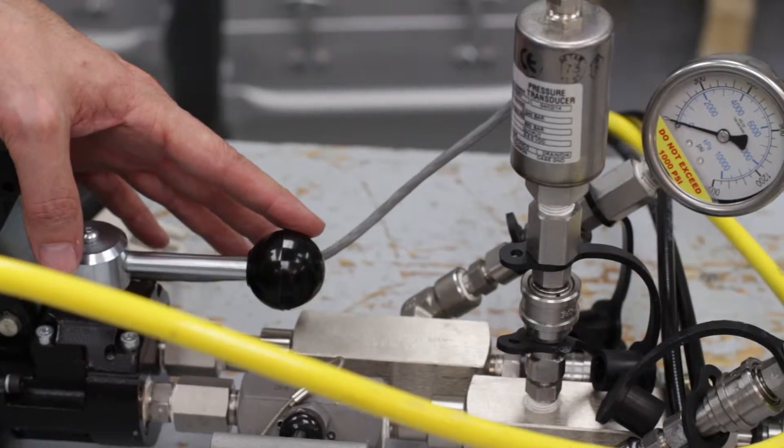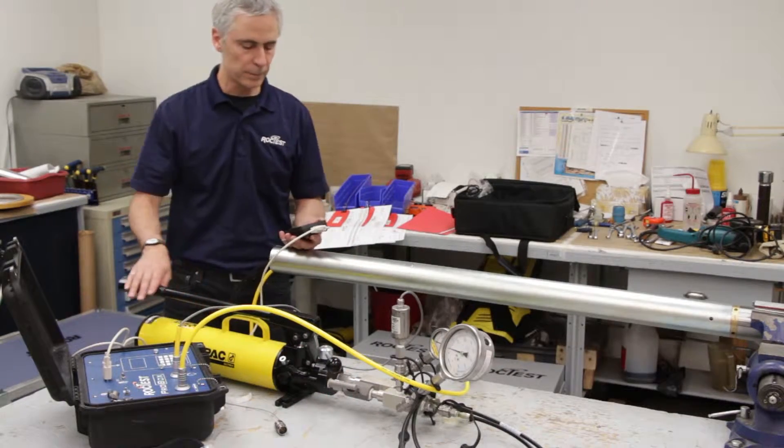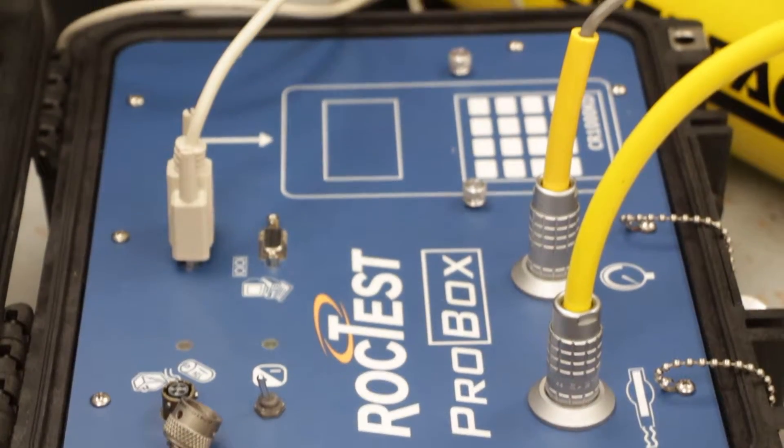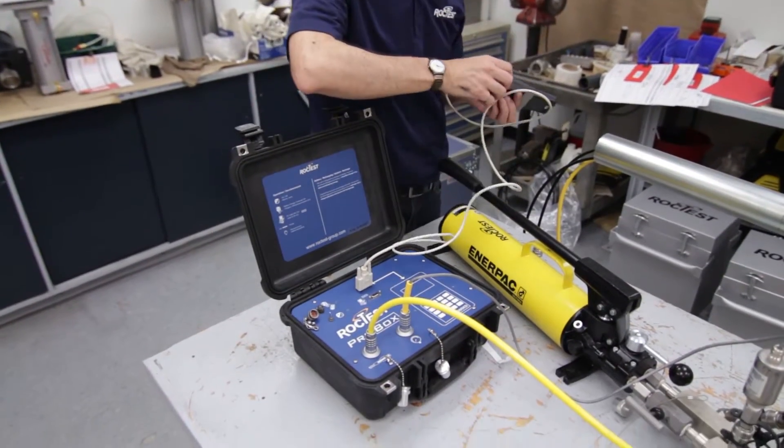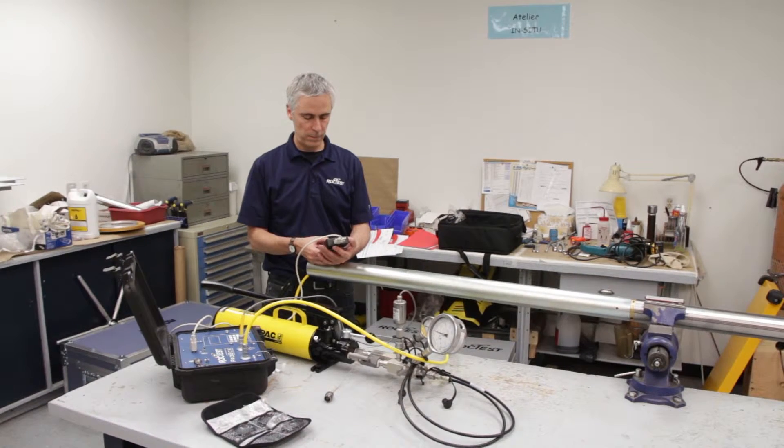Place the pump's small handle on position 1 and activate the pump to displace the piston to the end of its range. Maximum range is reached when the volume displayed on the ProBox stabilizes at around 676 cc.